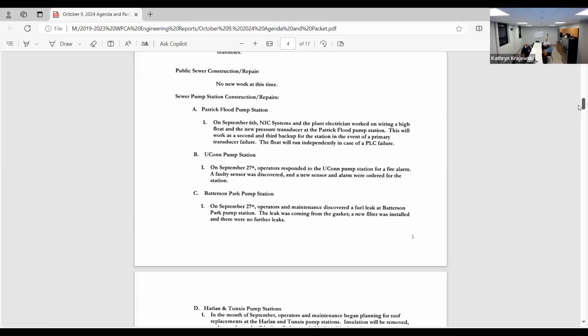So for stations, Patrick Flood Pump Station, we wired a new high float and a pressure transducer. We had a fog rod that was based on relays. The problem with the fog rod was it sits in the wet well, so when it gets coated with debris or grease, it would always throw it off. If you had a relay failure, it would also throw it off. So we replaced it with a float and then, I'm sorry, with the pressure transducer.